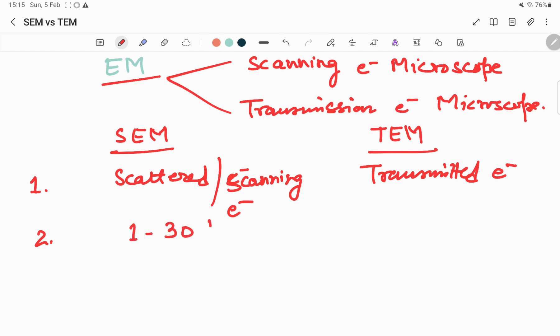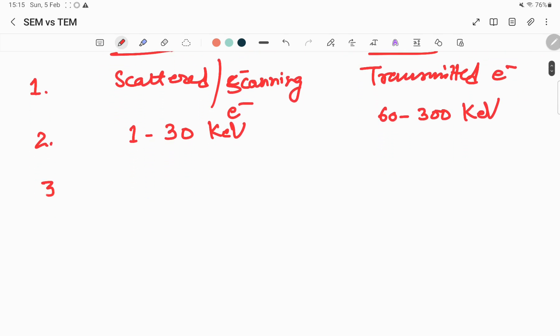The second basic difference is voltage. In SEM we use a voltage from 1 to 30 kilo electron volts, and in TEM we use a higher voltage of 60 to 300 kilo electron volts. The third basic difference is resolution: in SEM the best possible resolution is 10 to 20 nanometers, while in TEM the resolution goes down to 1 to 3 angstroms.